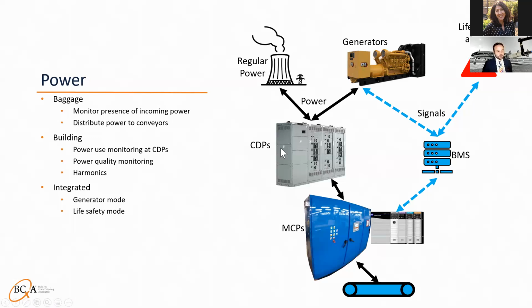The base building services monitor power use at the CDP level and also should look for power quality monitoring. One of the key things we found is harmonics being a main problem in terminals. Baggage handling systems contain VFDs, and those impart harmonics on the line. In addition, other things that aren't related to baggage at all, such as LED lighting, can do that, and that can cause unintended interference, either on baggage systems or on other things. Also, wear and tear on different equipment has been seen with those harmonics.